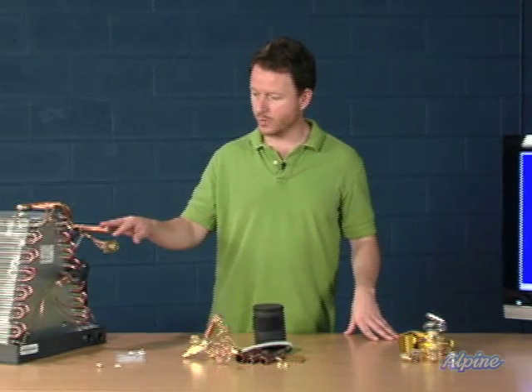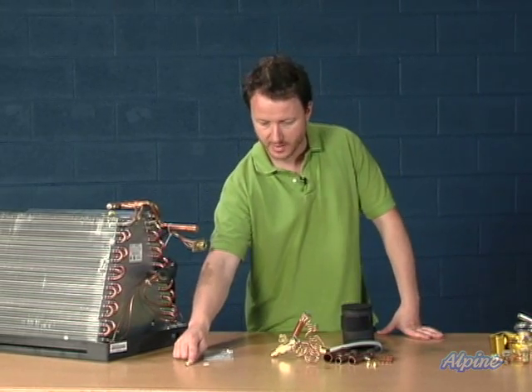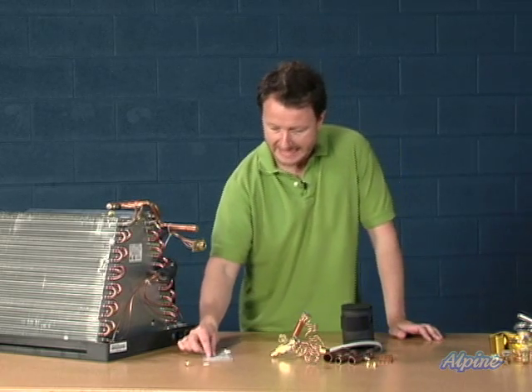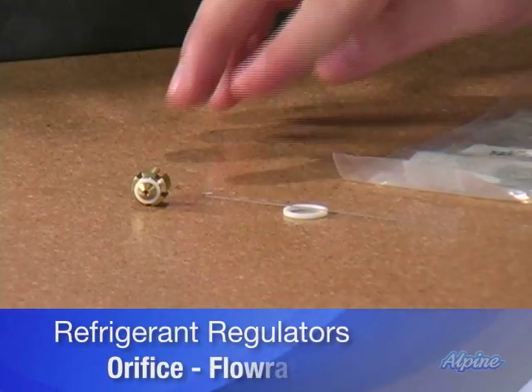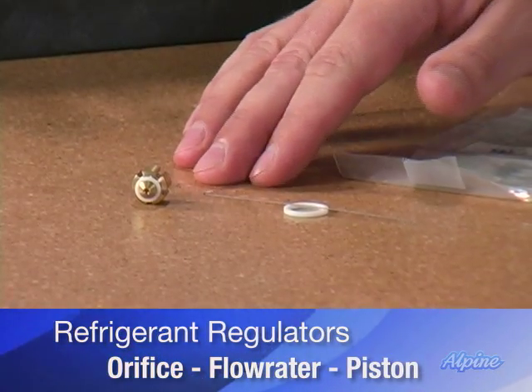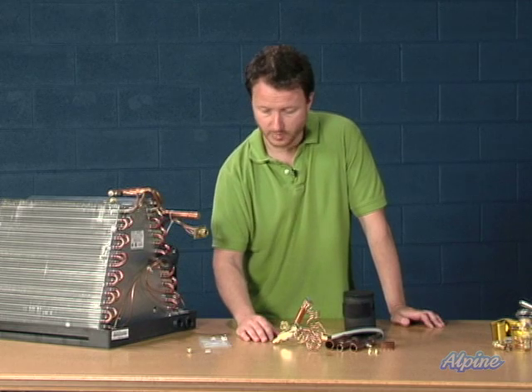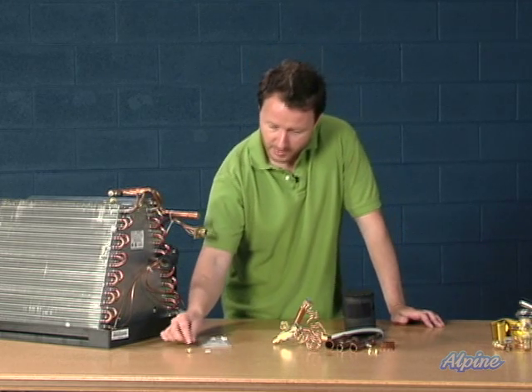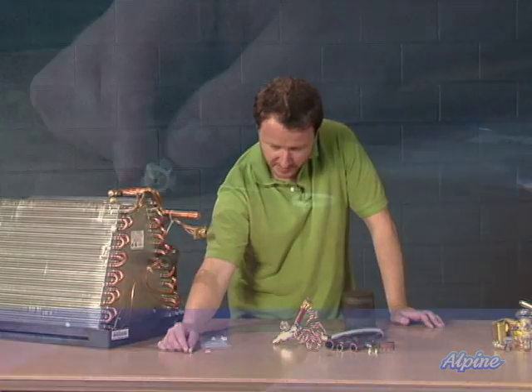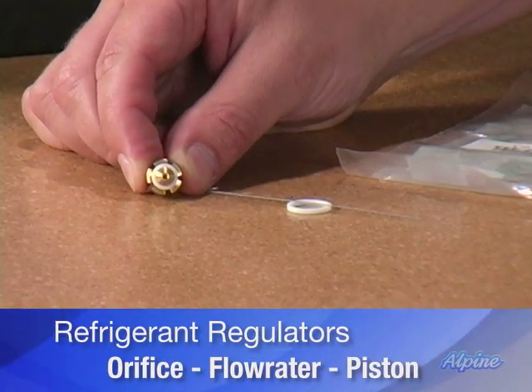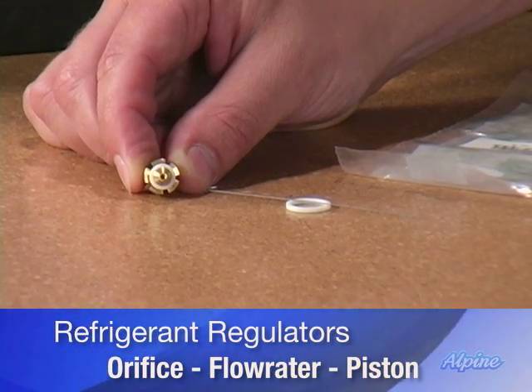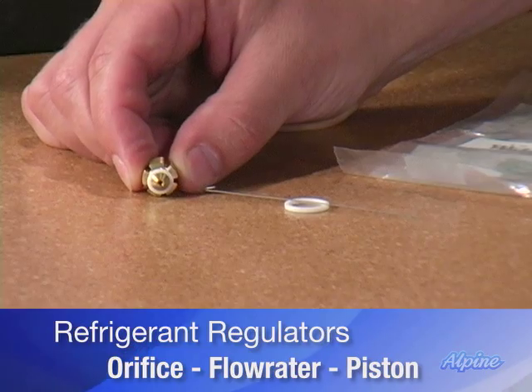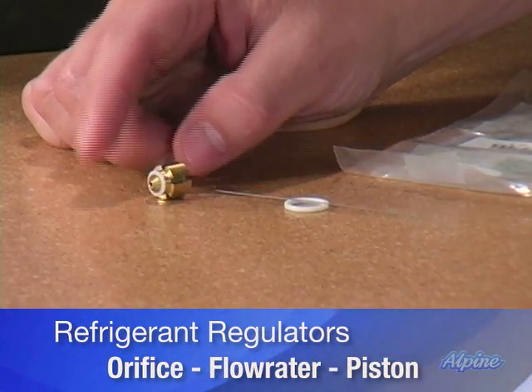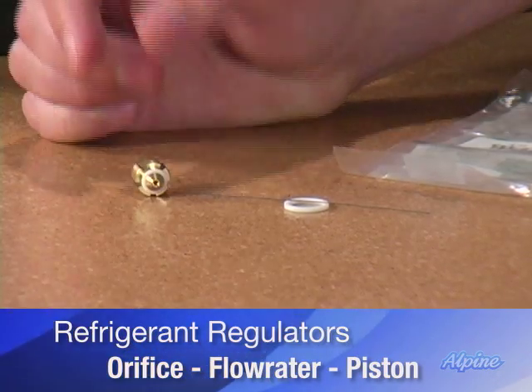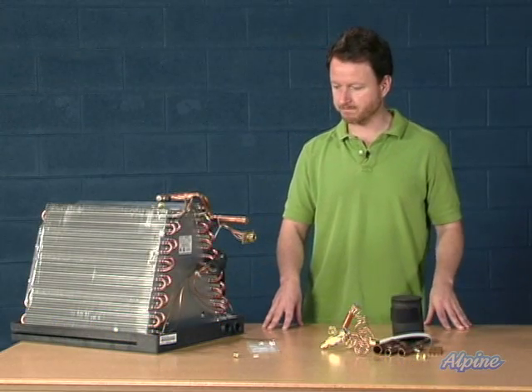Now, typically a system will come with an orifice, and we've got one sitting right here for you, or piston installed in it, and you might be using that. Lower efficiency systems can often operate with that exclusively, whereas the higher efficiency systems often require the thermostatic expansion valve. But as you can see here, this tiny little piece of brass has a precise hole drilled in the middle, and these come in a few different sizes depending upon the tonnage and efficiency of the air conditioning system you're installing. It's a pretty low-tech but crucial component to an air conditioning system.